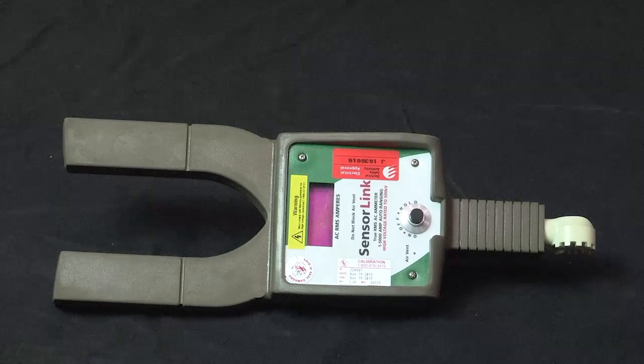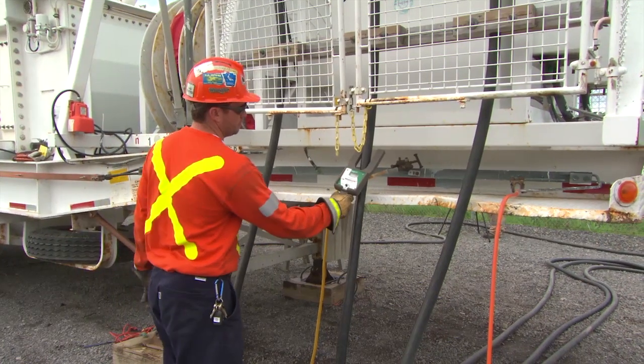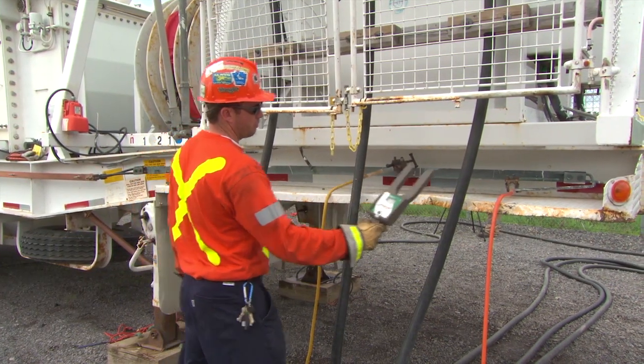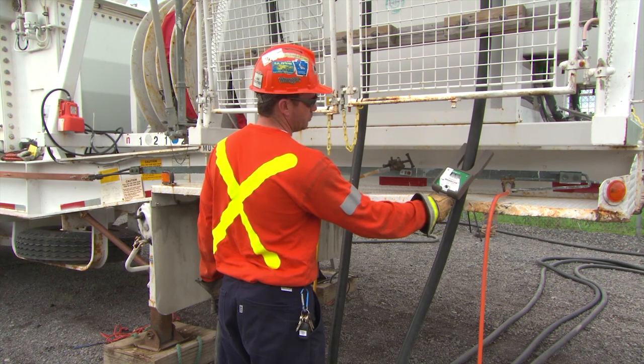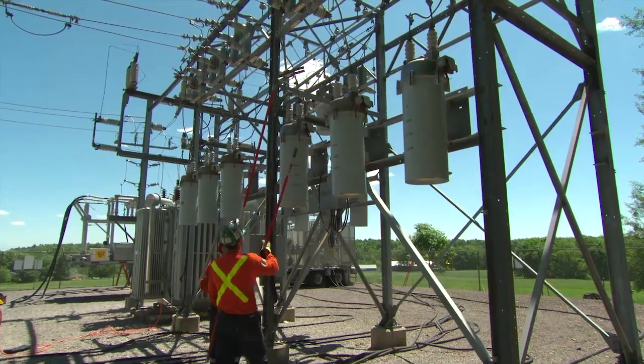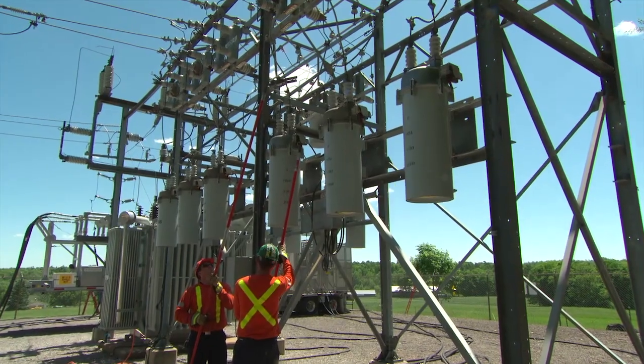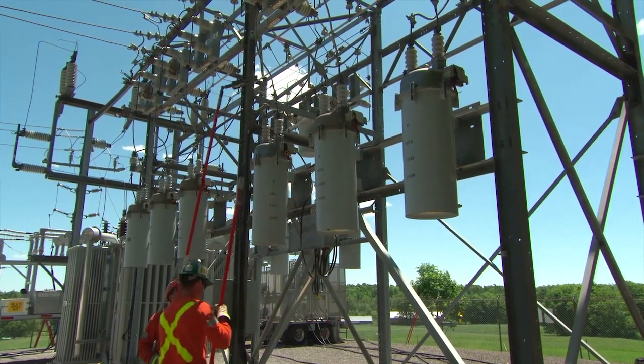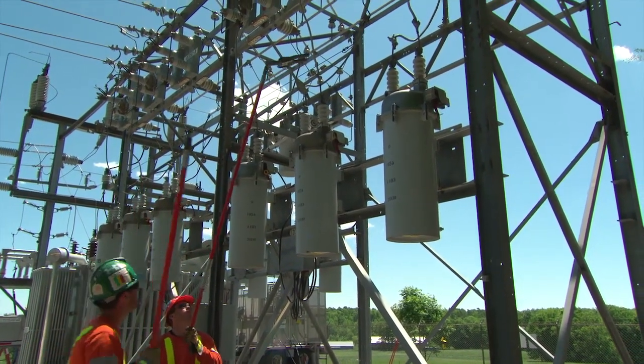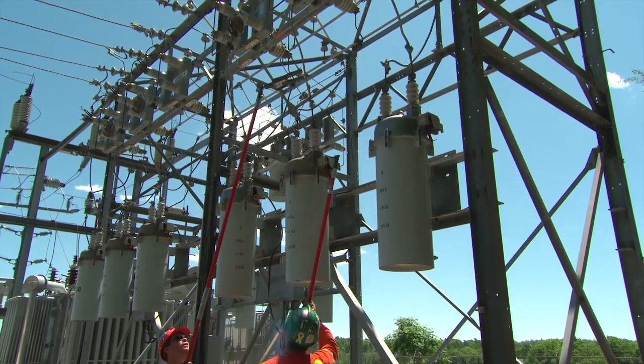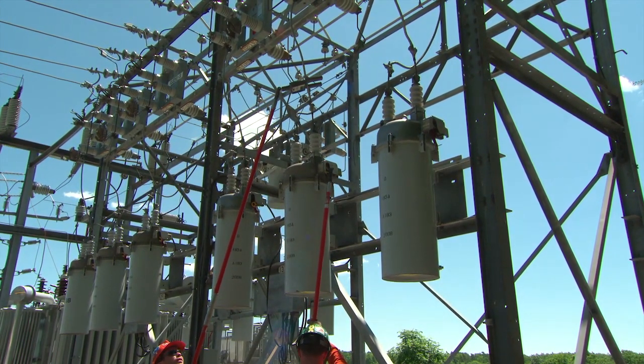Ammeters are used to check the current on live lines. When installing the MUS, you will need to check current on the MUS feeder cables and the DS feeder lines. When overhead lines require testing, you must clip the ammeter to the top of a live line stick, which allows you to raise the ammeter to the desired height and maintain proper working clearances.